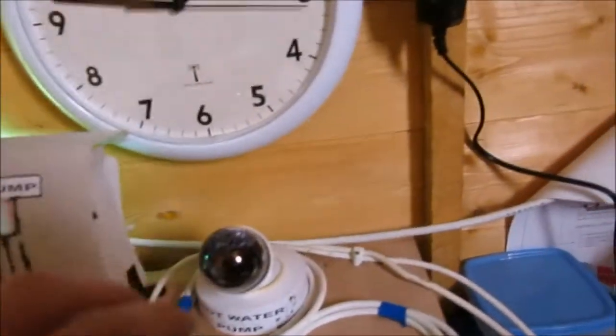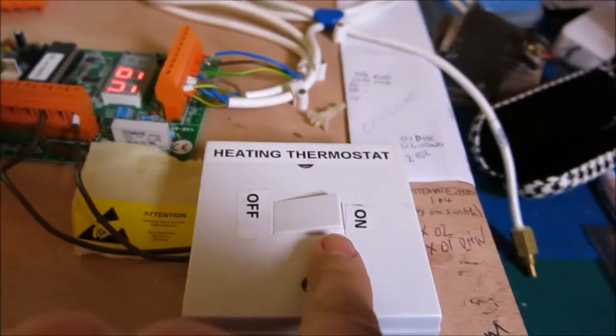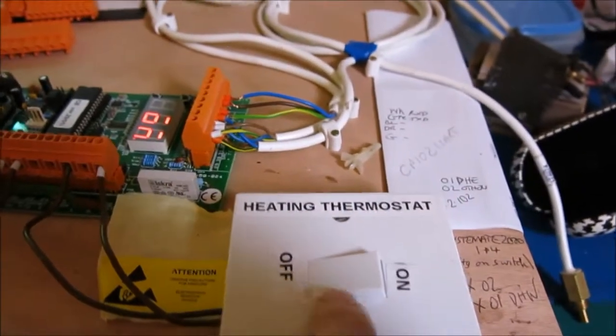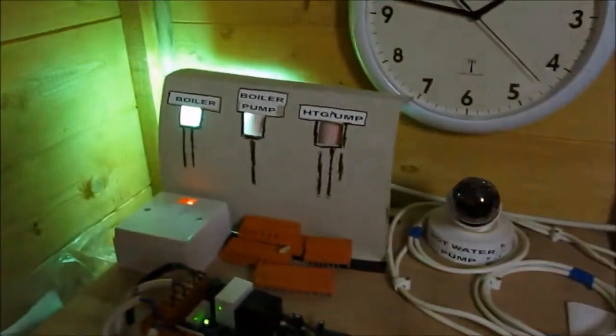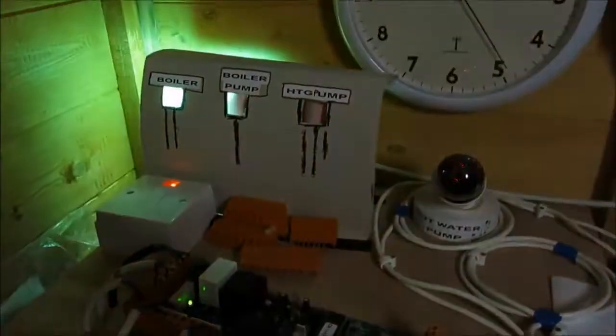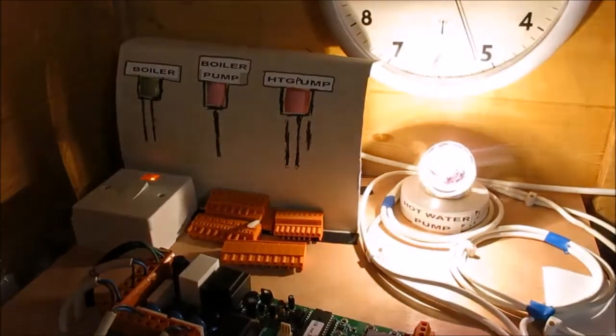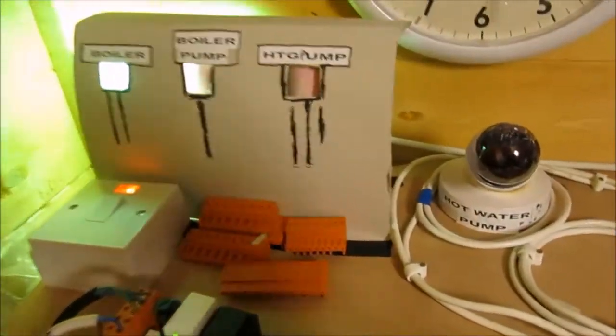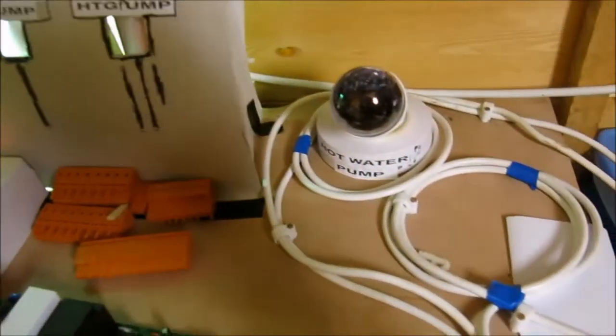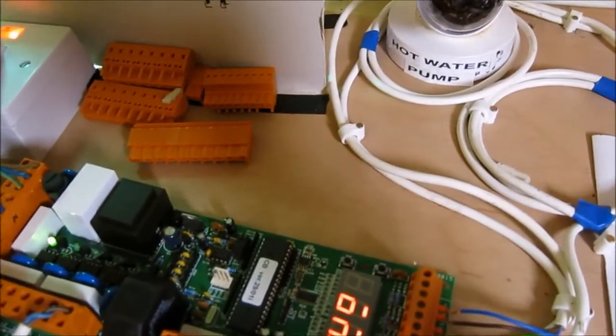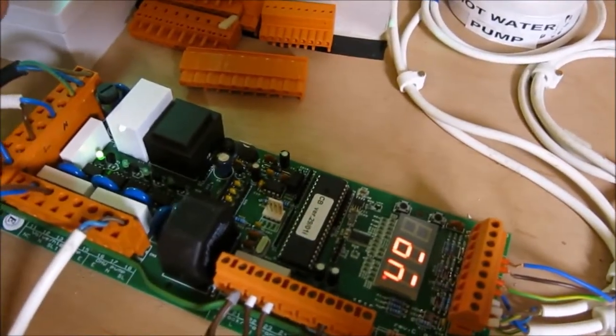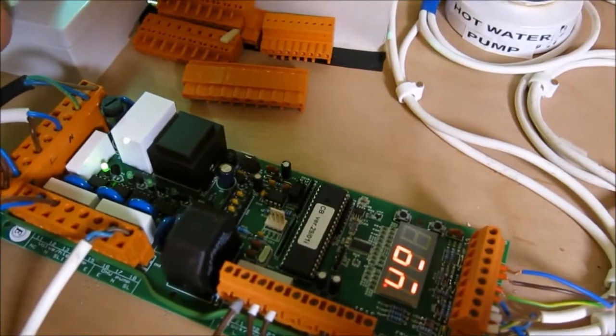The reason that went from low speed to high speed was because if you have the room thermostat turned on, I've got a switch simulating it here, you can actually flick in the self-test mode between high speed on the plate heat exchanger pump and back to the boiler. Now obviously it's just a test mode that you wouldn't run in that for any length of time. It's really just to pulse the outputs to check them. Okay, thank you.